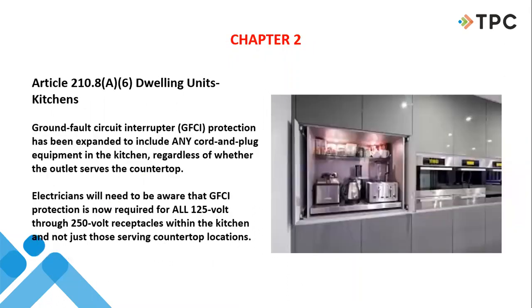This is an interesting one. Ground fault protection has been expanded to include any cord and plug connected equipment in the kitchen, regardless of whether the outlet serves the countertop. They kind of explain here, electricians will need to be aware that ground fault protection is now required for all 125 volt through 250 volt receptacles within the kitchen, and not just those serving countertop locations.